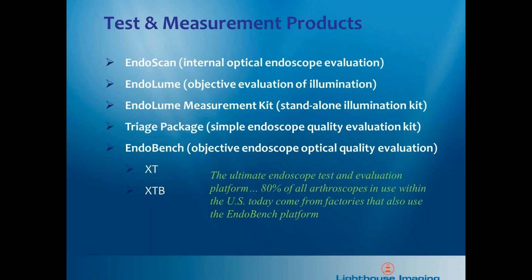these components. So that's one of the most common errors or problems in surgery: a dim image. And when that happens, often a biomed will simply replace the simplest components. So swap a cable quickly, maybe put a new bulb in the light source. But at that point, they're just reacting and trying to solve the problem however they can instead of using tools to actually isolate the problem and determine exactly what it is. So the EndoLume allows you to test these components very thoroughly and know for certain whether they're good or bad or even just on the edge.